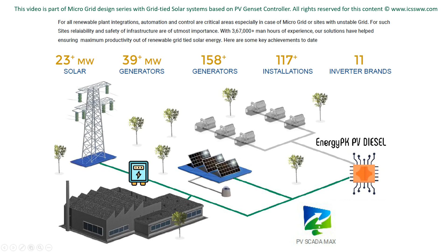First, let's be very clear that the variable, which is active power, is controlled by the zero export device on an instantaneous basis. The zero export device monitors active power and dispatches commands to the solar inverter to either increase or decrease solar generation. Logically, if the DC is strong and the inverter is able to take up all the load, it is quite normal to expect 0 amperes on the grid side. We still see those amperes because of the following reasons.